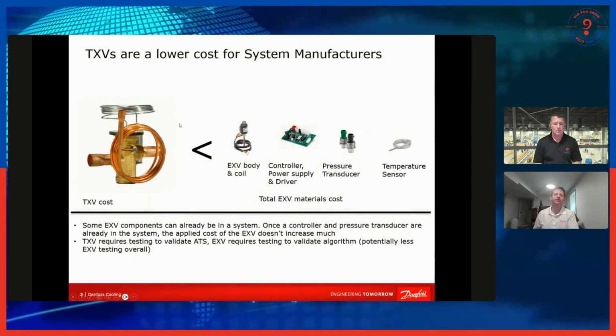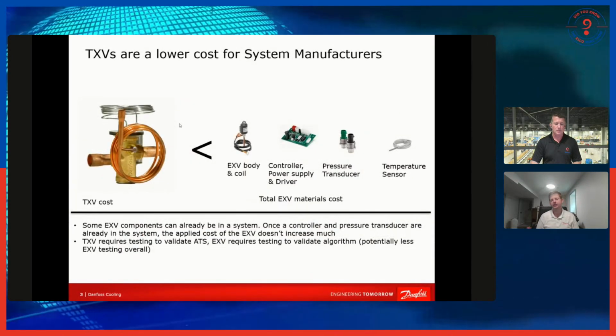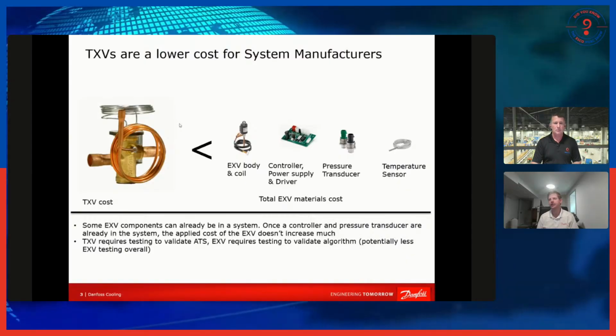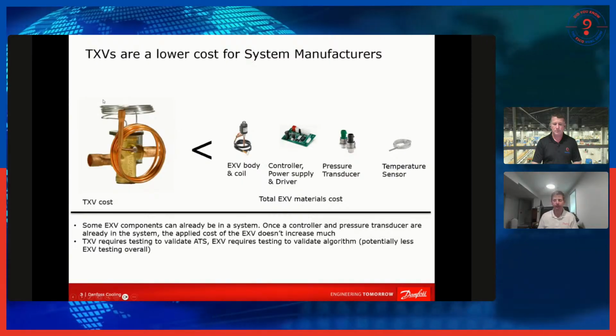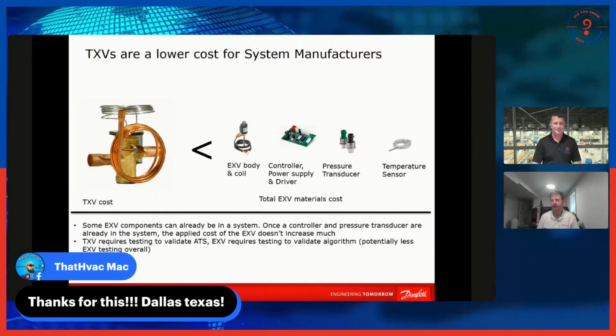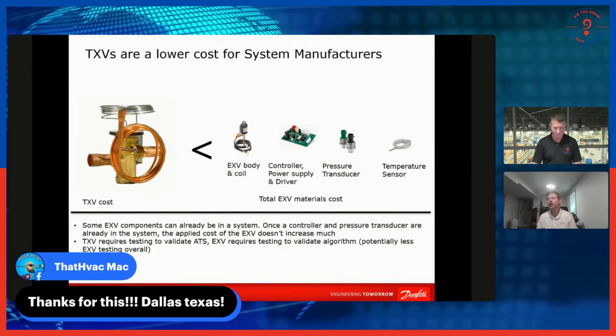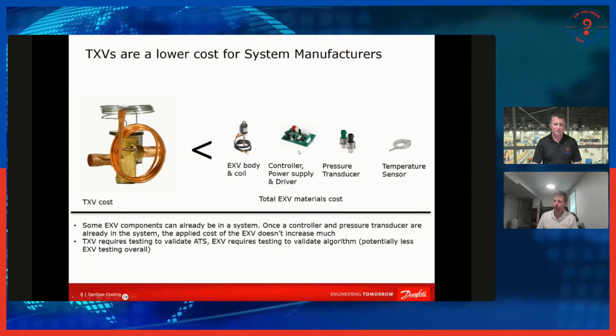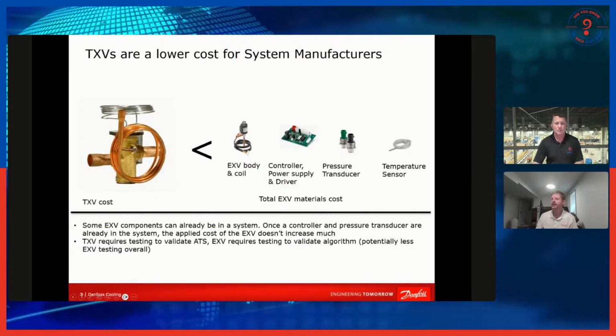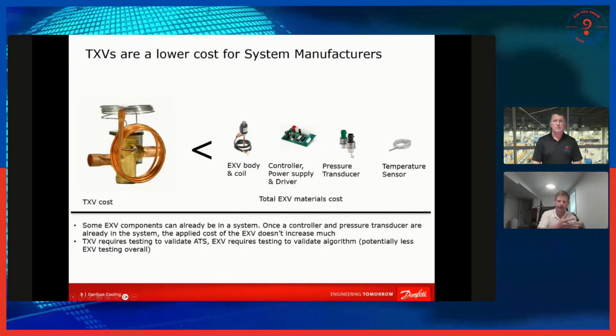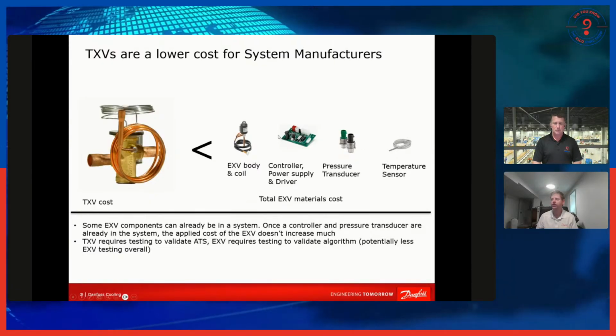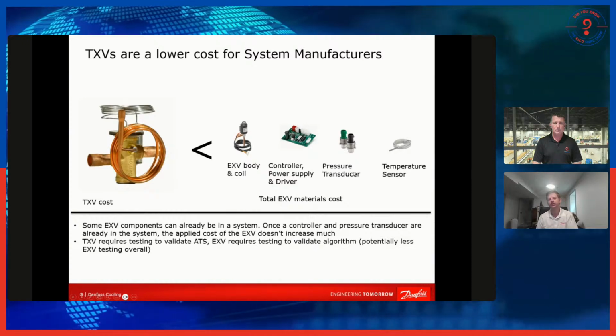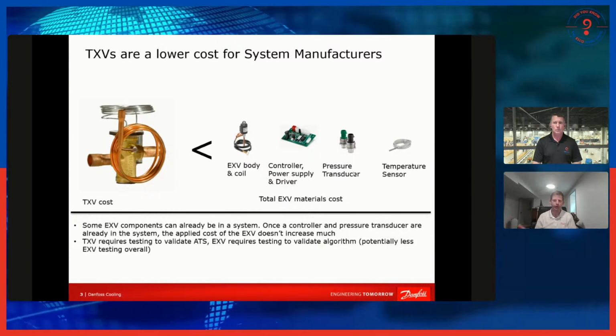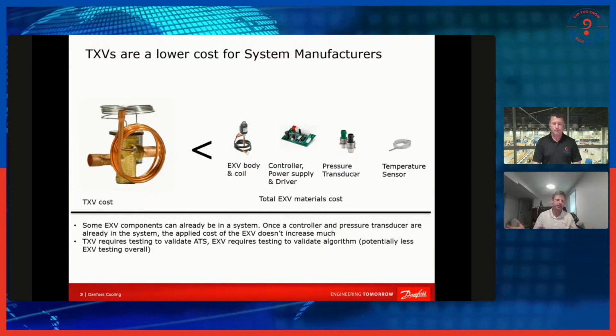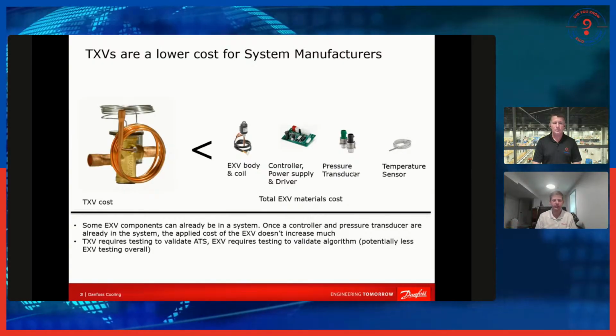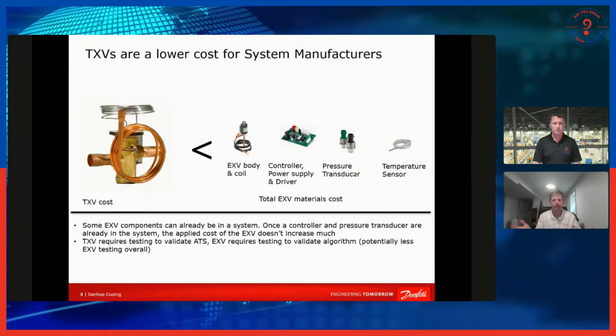The first one's just kind of getting down to brass tacks. A TXV is going to be a lower cost than an EXV. And the reason for that isn't because of the valve itself. A TXV versus an EXV, oftentimes they're very similar in price. What makes an EXV more expensive is you need a controller, and that controller has to have a power supply. And then you have to have sensors to measure pressure, and sensors to measure temperature. When you add all those extra items up, it makes an EXV overall more expensive than a TXV. So all things being equal, a manufacturer is going to prefer to use a TXV because it makes for a lower first cost.